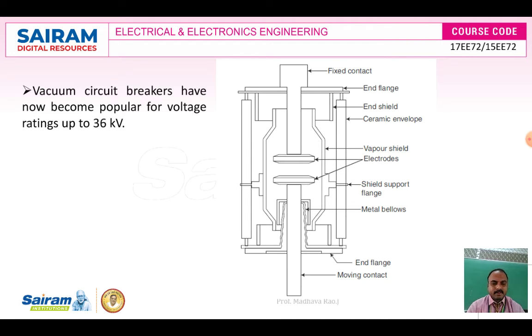Only one operation is common to all circuit breakers. Whenever a fault occurs, the arc will be extinguished between these two contacts. Due to the arc, these two contacts will separate, but the medium inside the circuit breaker will be different for different circuit breakers. Here we are using vacuum. It is popular for voltage ratings up to 36 kilovolts. So we can use these circuit breakers up to the 36 kilovolt range only, not above 36 kilovolts. Whenever an arc occurs, the moving contact moves away. That is the one operation common to all circuit breakers.